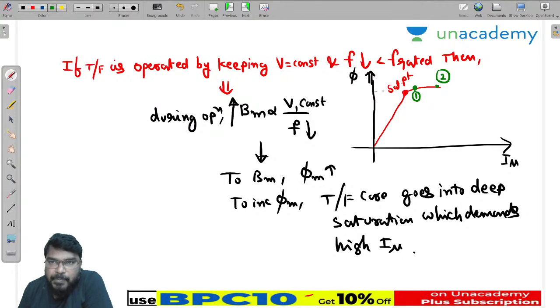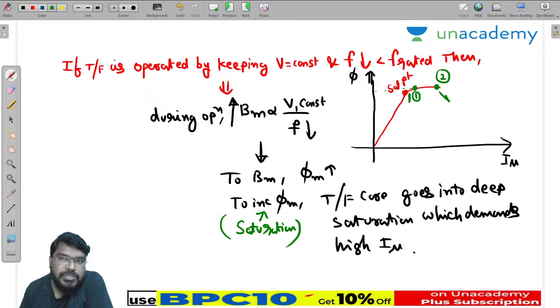So to increase the flux in the saturation region, more of the transformer core goes into deep saturation. There is low saturation and deep saturation. Since the transformer core goes into deep saturation, it demands high magnetizing current.